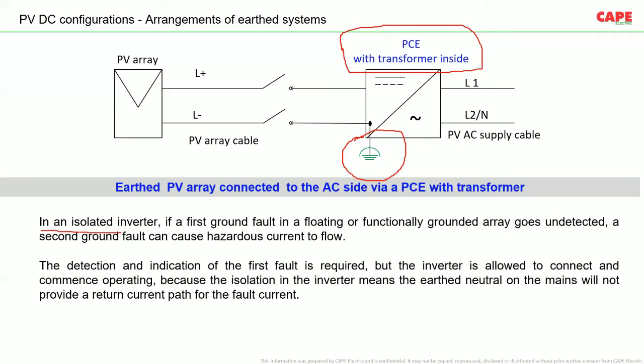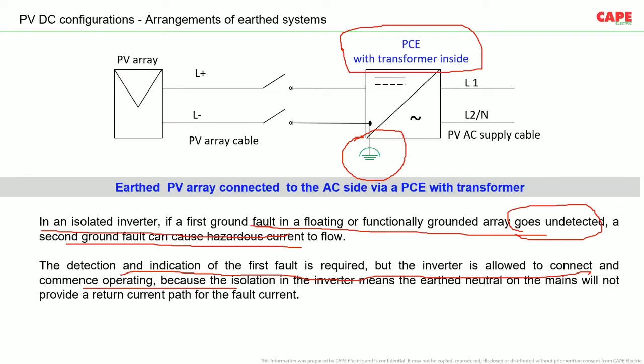In an isolated inverter, if the first ground fault in a floating or functionally grounded array goes undetected, a second fault can cause a hazardous current to flow. The first fault may not be dangerous, but the second fault may be very dangerous. So the safety measure to be implemented is that the first fault itself must be detected and avoided. So detection and indication of the first fault is required, but the inverter is allowed to connect and commence operation because the isolation of the inverter means the earth neutral of the mains will not provide a return current for the earth fault.